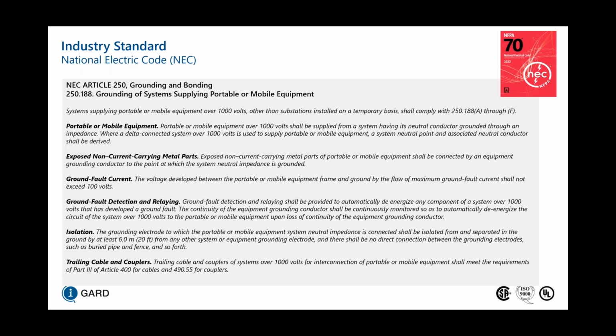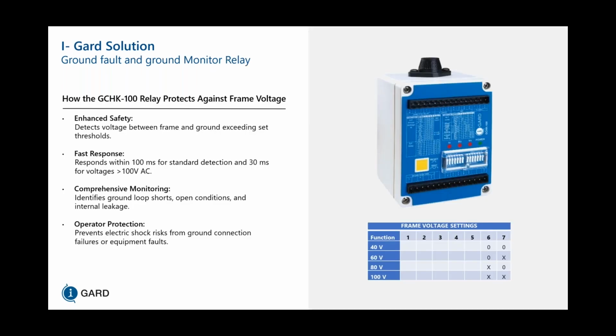For trailing cable and couplers of systems over 1,000 volts for interconnection of portable or mobile equipment shall meet the requirements of Part 3 of Article 400 for cables and 490.55 for couplers. So at I-Gard, we do have a solution in terms of ground fault ground check, and that is our GCHK 100 relay.